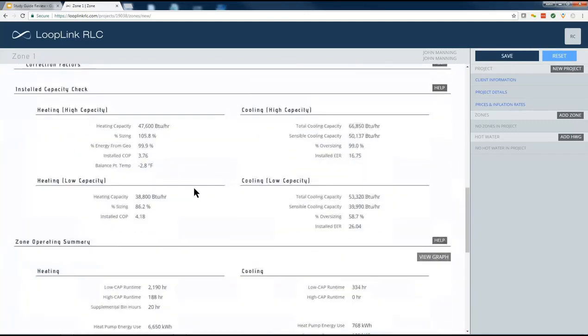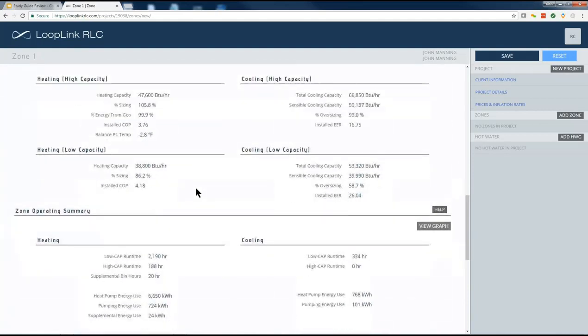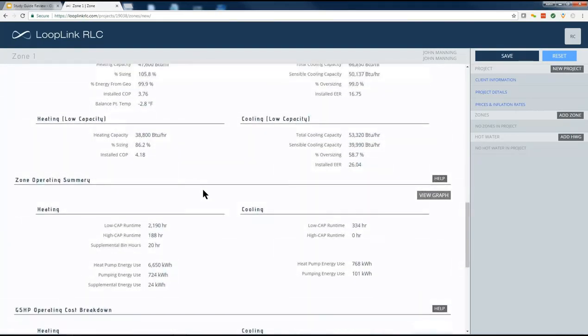I'm going to back up and choose a different unit because we could probably take a look at another one that might fit the system a little better with respect to first costs relative to operating costs. But just taking a look at this 5-ton unit now, you can see the predicted low capacity runtime in heating mode is about 2,200 hours versus 200 hours of high speed runtime. So not a whole lot of hours relatively speaking in high speed for this unit. And then obviously on the cooling side, we're running in low speed 100% of the hours of the year.